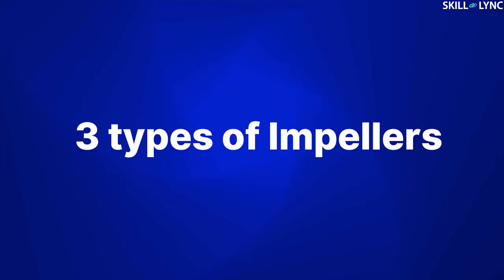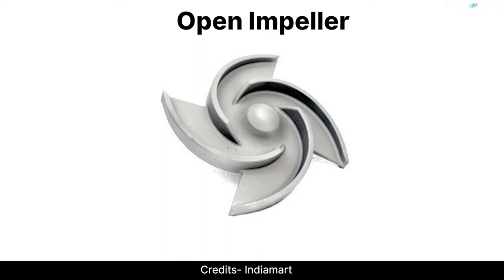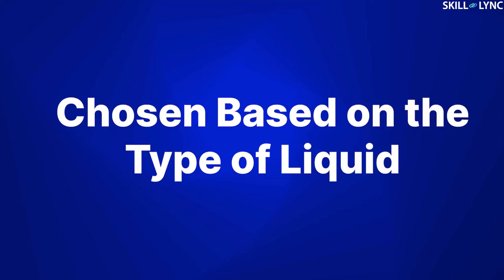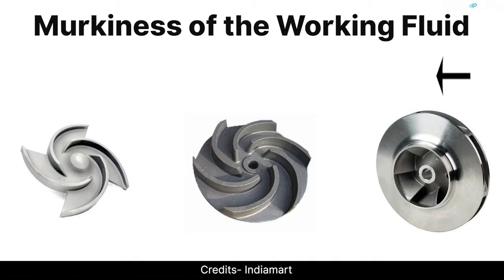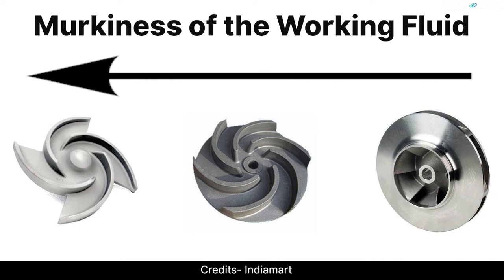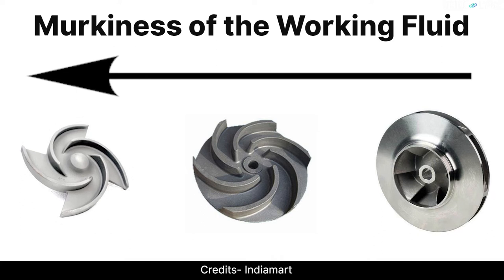There are three different types of impellers that are commercially available: the open type impeller, the semi-open impeller, and the closed type impeller. The impeller type is chosen based on the liquid. If the working liquid is cloggy and has a lot of sediments in it, an open type impeller is used. If the working fluid is clean with no impurities, a closed type impeller is used. If a closed type impeller is used in murky water, the impurities in the water can clog the impeller and prevent it from functioning properly.